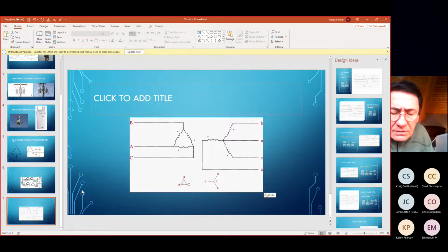Above a certain horsepower rating in our product, and I believe that's above 40, correct me if I'm wrong, Craig, we already will install the equivalent of a 3% input line reactor. It's called a DC bus choke. And while it's in a different part of the circuit, the inductor is placed on the DC bus positive rail. It is the electrical equivalent of a 3-phase input line reactor.